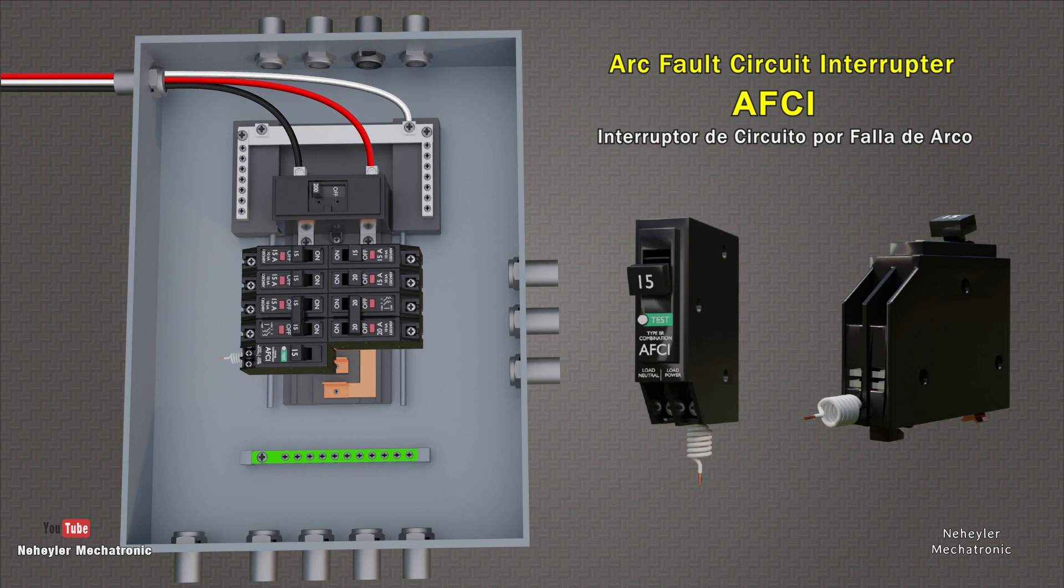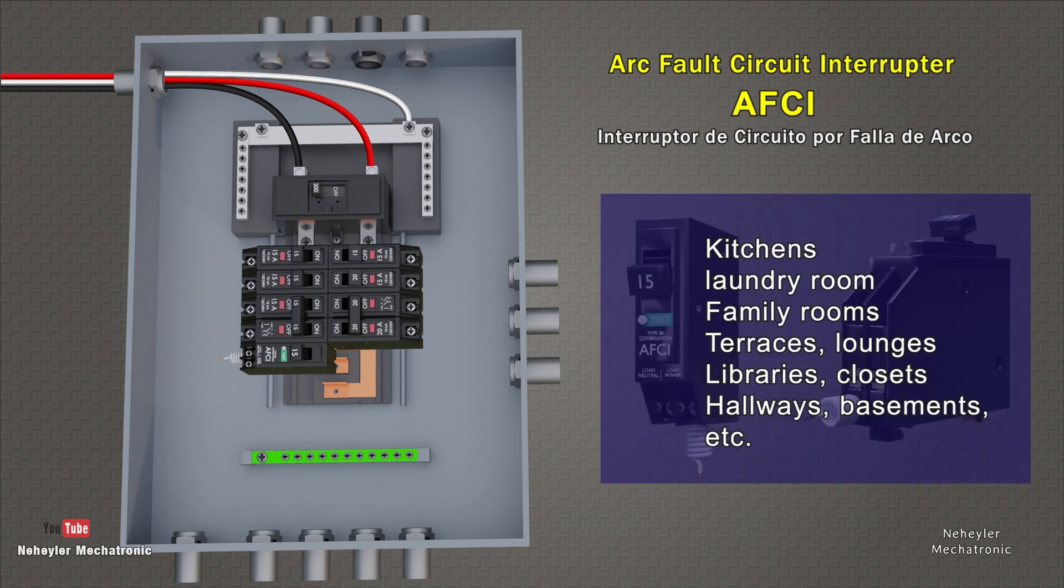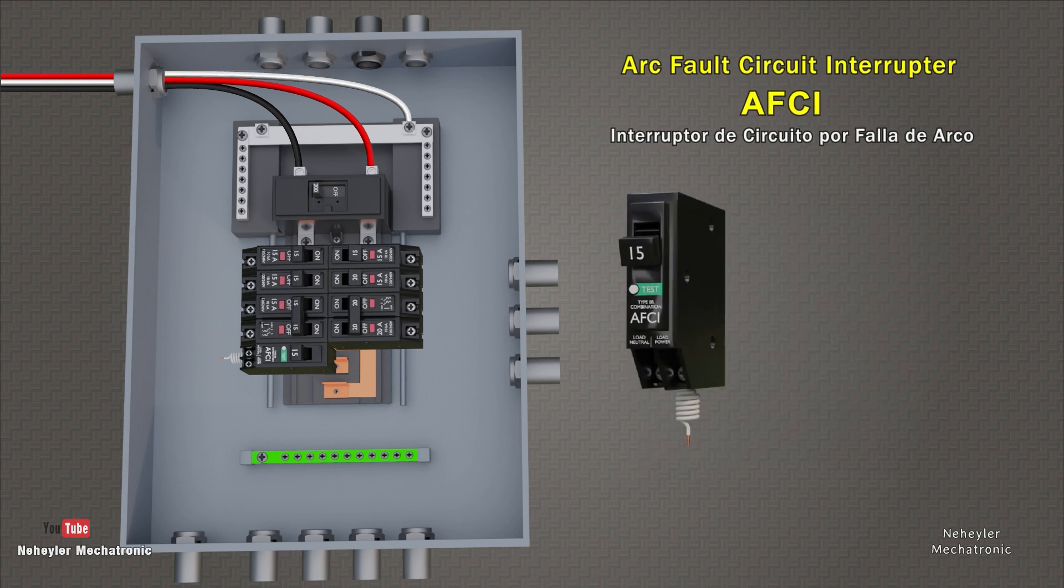On the front there is a test button for manual testing to confirm that the device works correctly. To this device, it is necessary to connect the neutral through the white cable. Also, it has two output terminals or terminals, where it indicates which side the neutral output cable and the hotline output cable should go. An explanation of the connection on the electrical panel will be seen shortly. According to the current National Electricity Code, it indicates that these devices should be used as protections in kitchens, laundry rooms, family rooms, terraces, living rooms, etc.